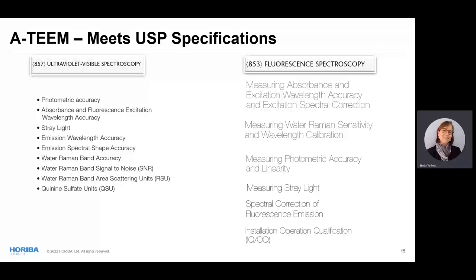As implemented on the Aqualog, A-TEEM also meets the USP specifications for both UV-Vis spectroscopy and fluorescence spectroscopy. Even though the combination of the two is a novel application, it's still using well-established spectroscopic methods for which there are USP chapters that define what you need to do in order to get validatable results. With traceable reference standards and automated methods, we are able to do that.